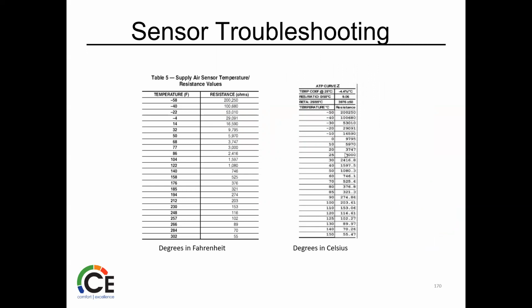And if you really are happy, there's a Celsius version there for it. We always want to try and troubleshoot a sensor at least two different ways. So you want to look at the chart and do your ambient sensor. But then the best thing, as we've talked about before, is to get some ice water, stick this thing in ice water and verify it a second time. Don't just go off your first reading because we're talking about resistance to temperature and a change, and it might be off. But if it's off twice, there's a problem.